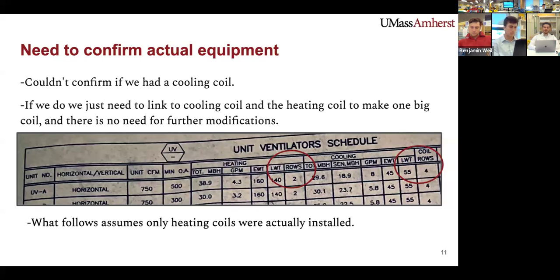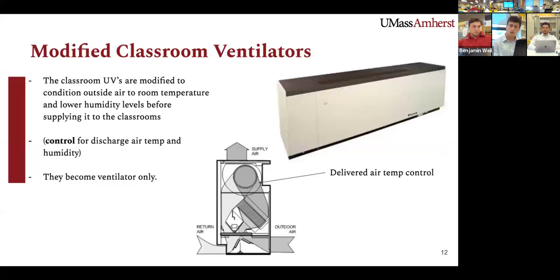The following recommendation assumes that there are only heating coils throughout the school. Currently a classroom unit ventilator provides fresh air. It tempers that air as well as providing heat. The unit ventilator needs enough heating capacity to do both and is able to do that with hot water. And this hot water is around 160 degrees.